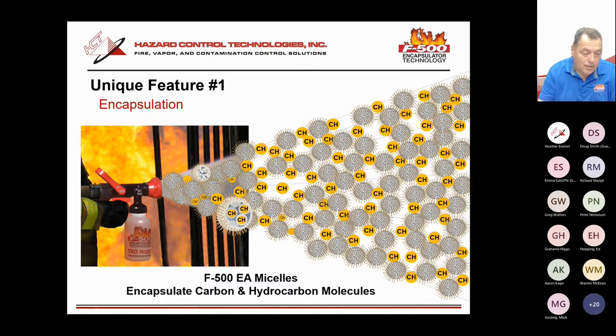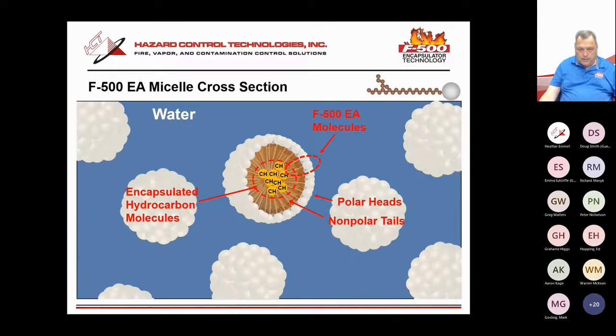That's one of the differences between F500 and water: the encapsulator agent encapsulates any exposed electrolyte within a chemical cocoon, a spherical micelle, thus rendering it non-flammable and non-ignitable, even if the temperature comes back, because we were putting temperature on that encapsulated electrolyte up to 1500 degrees F. That's one of the critical things here.